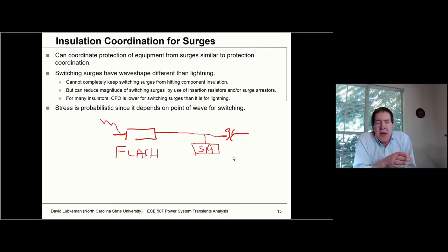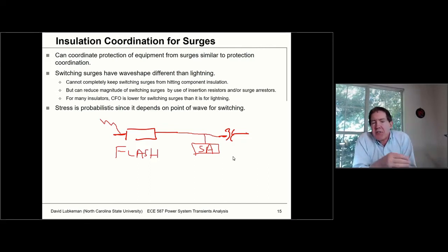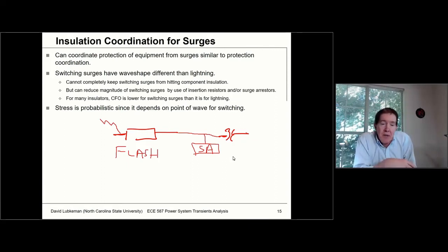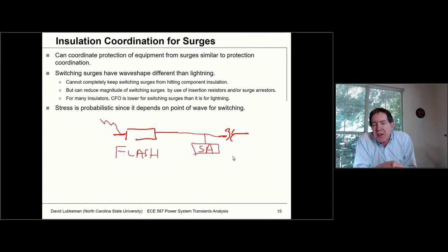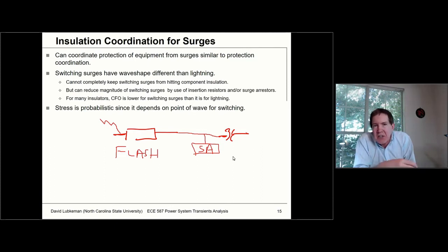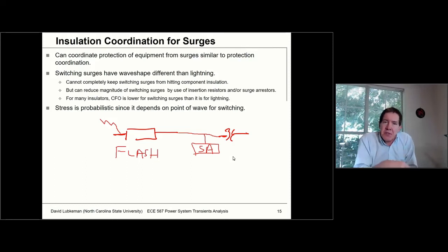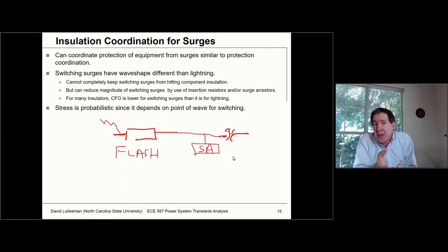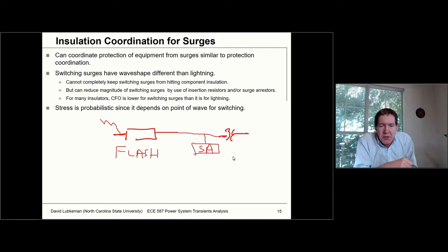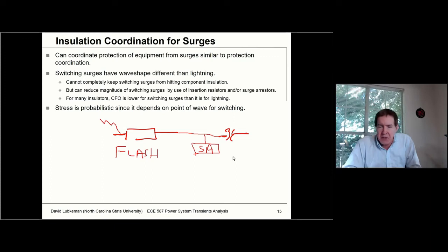Switching surges have different characteristics than lightning. Maybe a switching surge on the far left wouldn't cause a flashover and wouldn't even be caught by the surge arrestor. In that case, you can use pre-insertion resistors on the switches — when you switch in a voltage, the pre-insertion resistor minimizes the switching surge. This is the sort of thinking you'd have doing insulation coordination, similar to protection coordination, where you think about what components to add to the circuit to protect critical equipment like transformers.